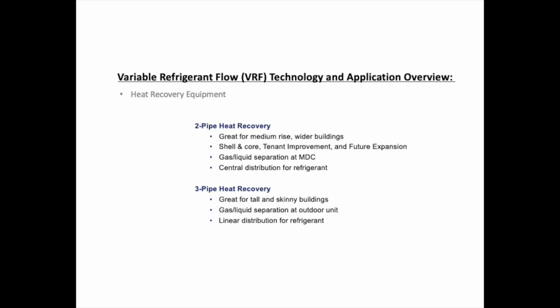So where would you use 3-pipe heat recovery? Typically mid to high-rise buildings would be great candidates for 3-pipe heat recovery systems. Hotels, office buildings, multifamily, these are good candidates for 3-pipe heat recovery system, to where you can mount the outdoor units up on the roof, and then you can pipe down and have a multi-port flow selector box on each floor, branch out, serve the different zones, and then continue down on to the rest of the building, multi-port box, branch out to different zones, etc., etc.